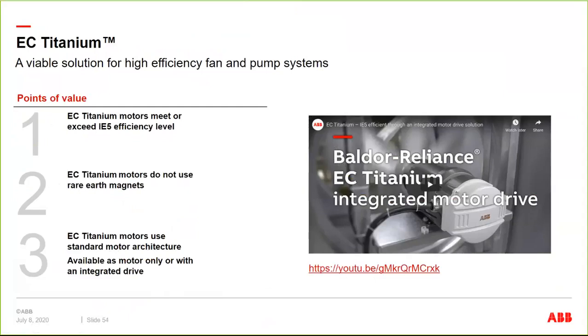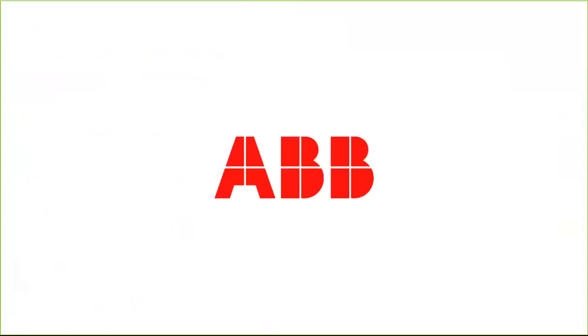But in summary, this product is designed around meeting IE5 efficiency levels. We don't want to use rare earth magnet materials, so that it's a readily available product, and we use standard motor architecture. One of the key things I really didn't touch on is that it's a drop-in replacement for a standard NEMA motor mount. There's nothing special or fancy about it. You can replace a standard induction motor with this, and it's just a bolt-in replacement. And it's available as a motor only or with an integrated drive.